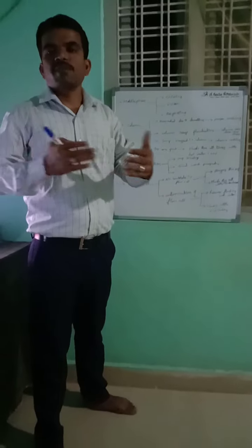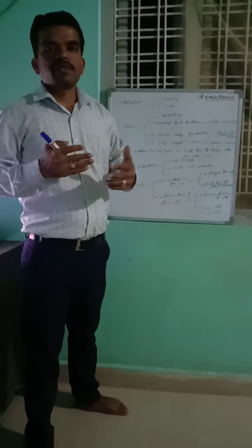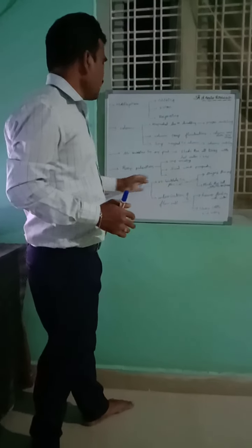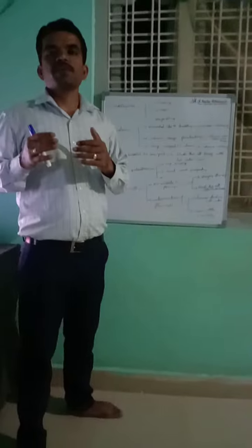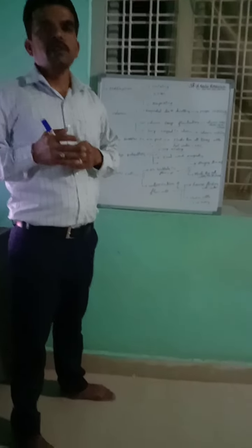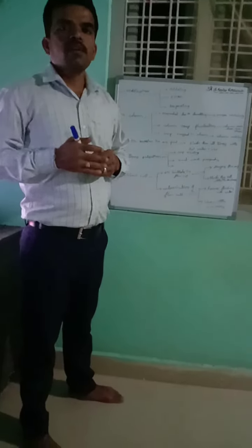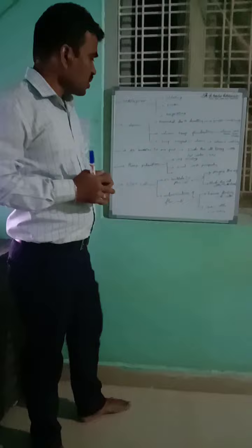Due to that, pulsation will happen. For that purpose, we will get some baseline disturbance and noise. Okay, and seal wash also we have to do properly. When you are getting pump pulsation, you have to do the seal wash properly. It may reduce some of the noise in our baseline. And the flow cell is also very important.